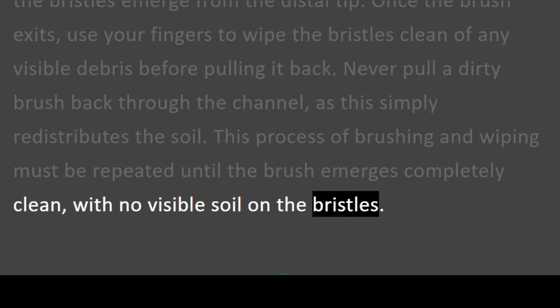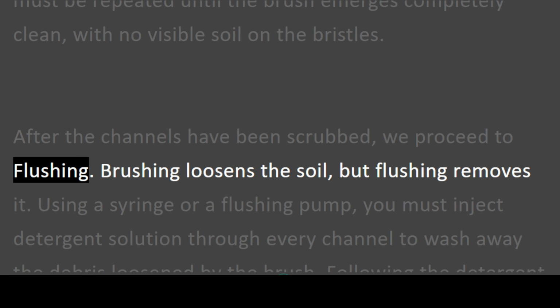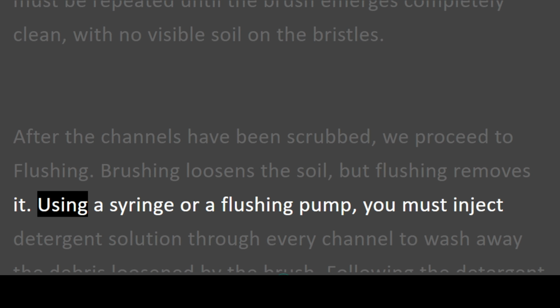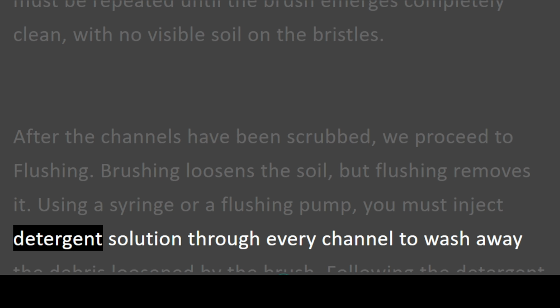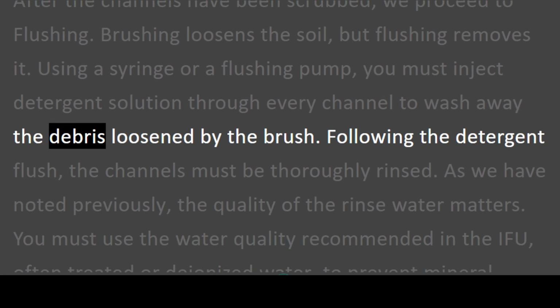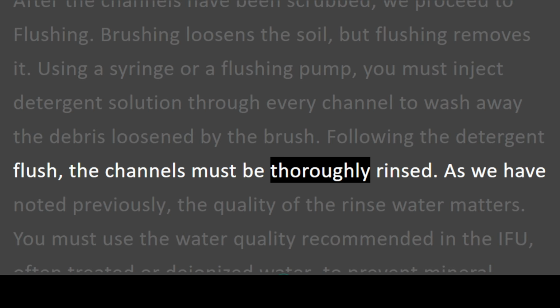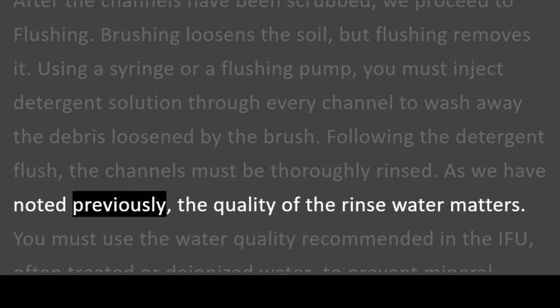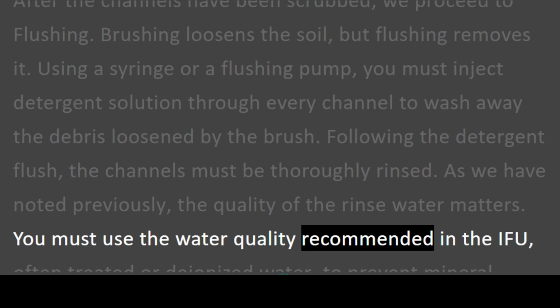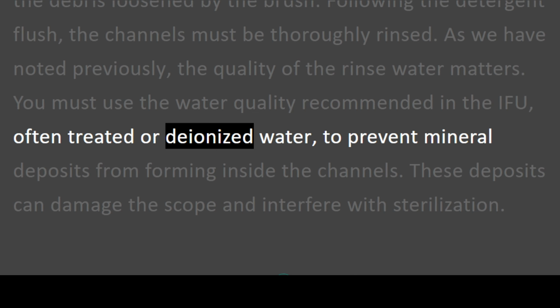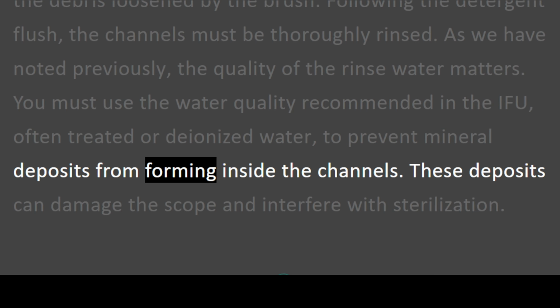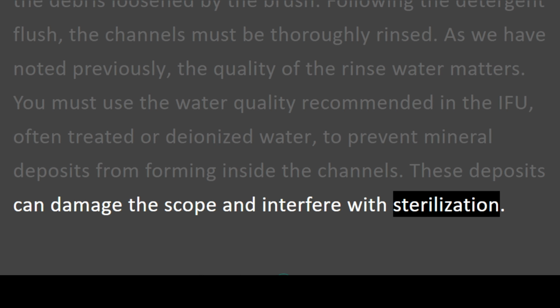the bristles. After the channels have been scrubbed, we proceed to flushing. Brushing loosens the soil, but flushing removes it. Using a syringe or a flushing pump, you must inject detergent solution through every channel to wash away the debris loosened by the brush. Following the detergent flush, the channels must be thoroughly rinsed. As we have noted previously, the quality of the rinse water matters. You must use the water quality recommended in the IFU, often treated or deionized water, to prevent mineral deposits from forming inside the channels. These deposits can damage the scope and interfere with sterilization.